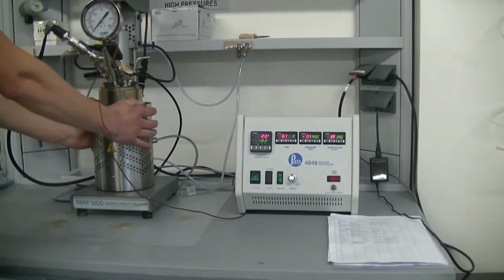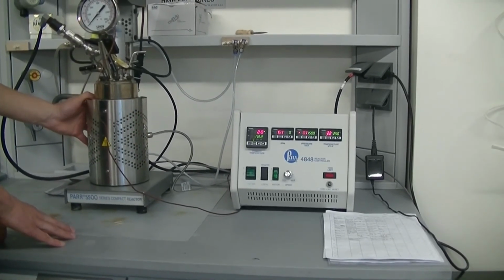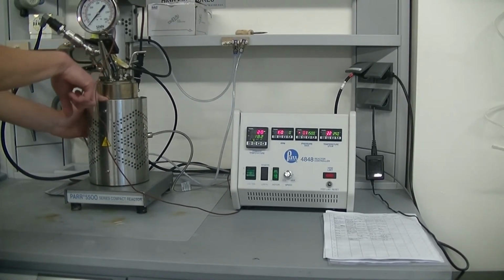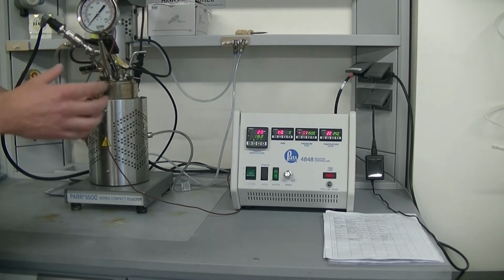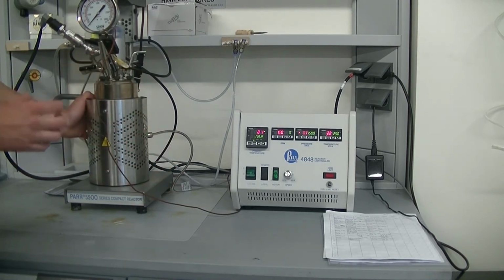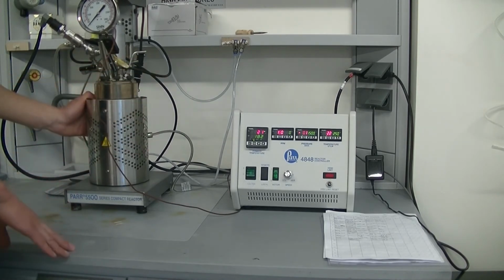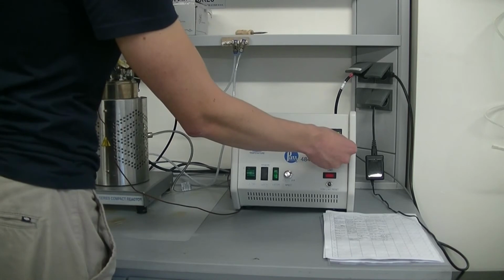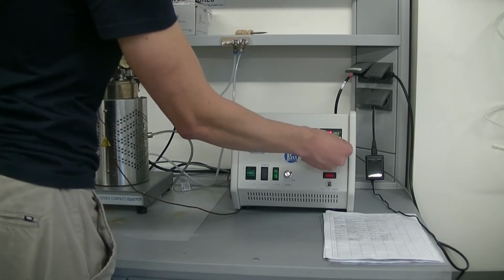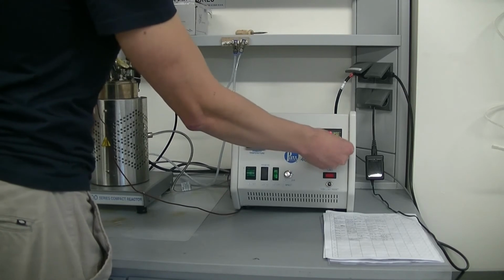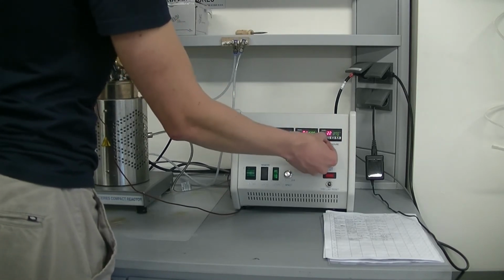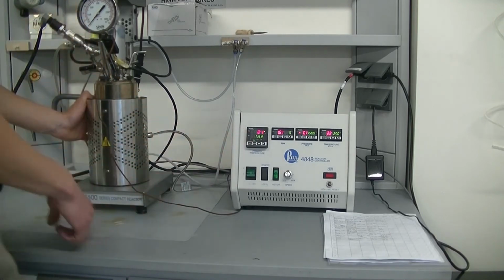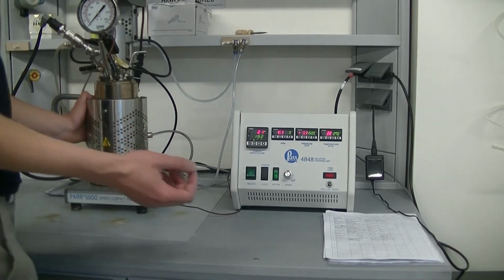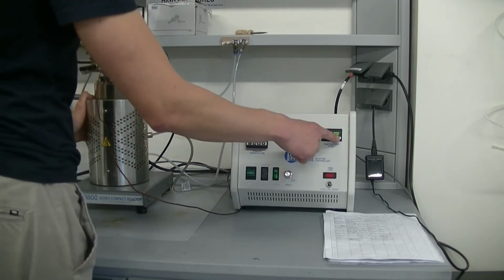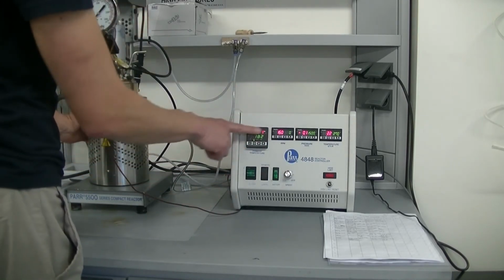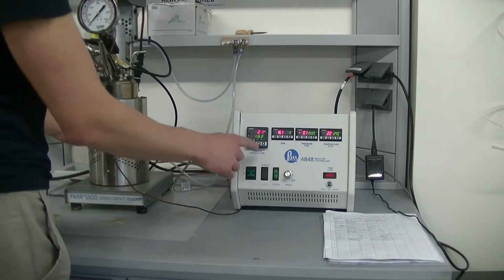However, it's not certain that the temperature inside will reach 250 also, because there is a big inertia between the outside and the inside of the reactor. So the recommended thing is to set something more here, like 270, and then we should be able to see something like 250 inside. If not, after some time we can come here again just to increase this temperature to equilibrate the temperature inside.